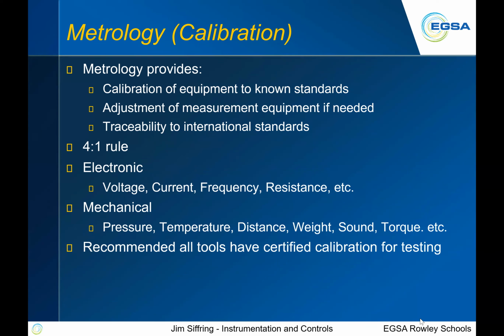So, what are some of the electronic things we do? Voltage, current, frequency, resistance. Mechanical things that we need to keep testing and calibrated are pressure, temperature, distance, weight, sound, torque, that sort of thing. Pretty much all those tools that measure any of those parameters need to have some sort of certification. I know at the plant that I work at, we even have tape measures that are calibrated. It's funny, you see a Stanley 25-foot tape measure with a calibration sticker on it, which always seems funny, but it's something you need to do, because tapes do wear out, the ends get loose, things like that happen. They need to be calibrated.